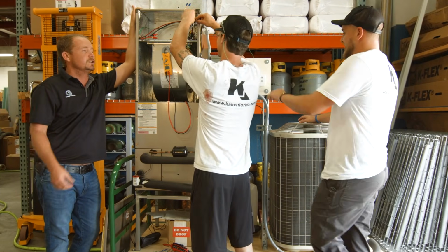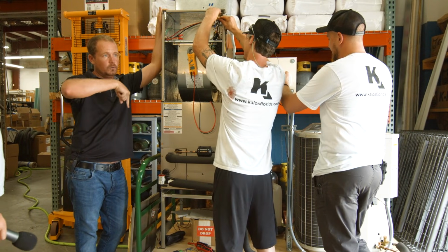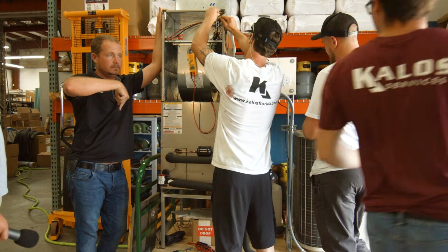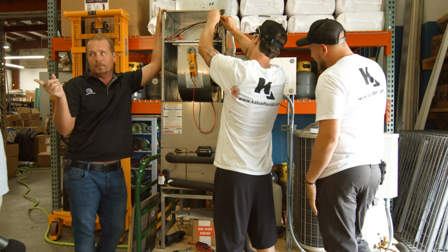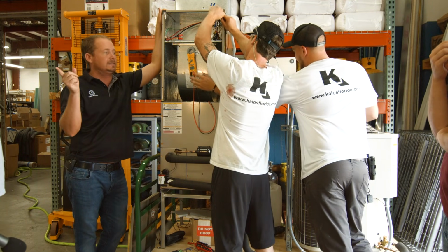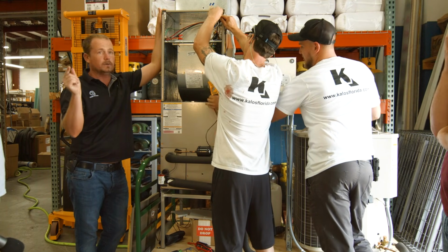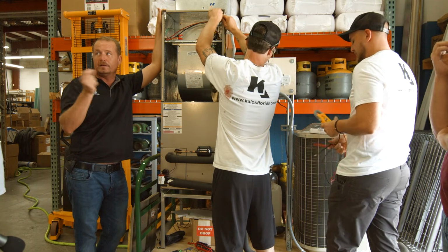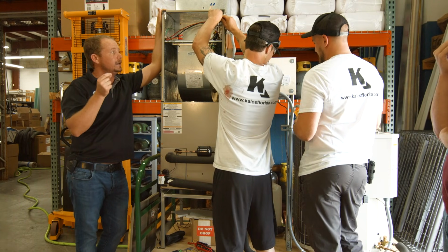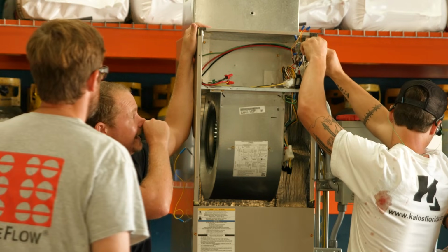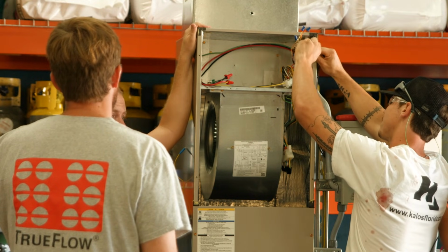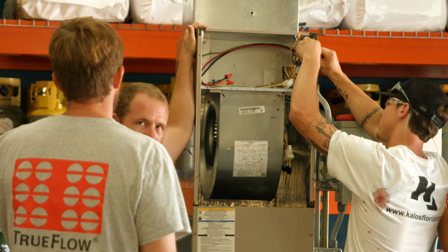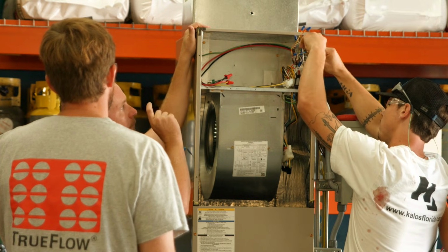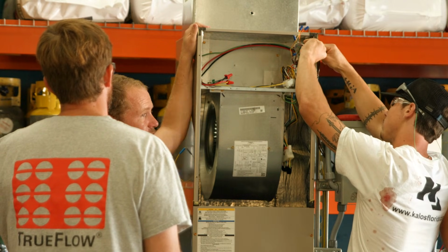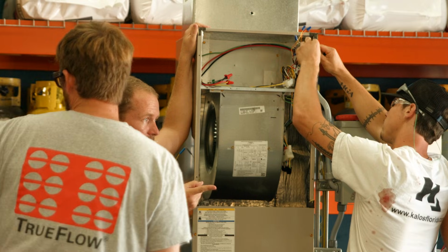All right, so Eric's method is using an ohm meter on a de-energized circuit, which is better for a couple reasons. One of the reasons that it's better is that you're not going to shock the circuit by continuing to energize it. And the other thing is that if we can get good connection without pulling the wire nuts off, this is the only downside of this, it's a little bit more of a pro move. If we can stick in there and get a connection to it on the other side of the wire nut, we don't even have to pull the wire nut off.